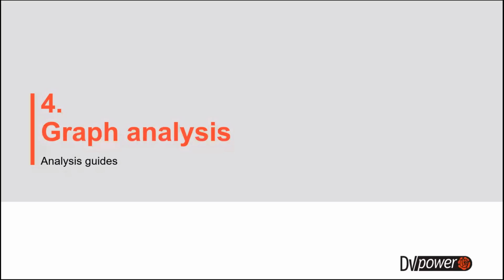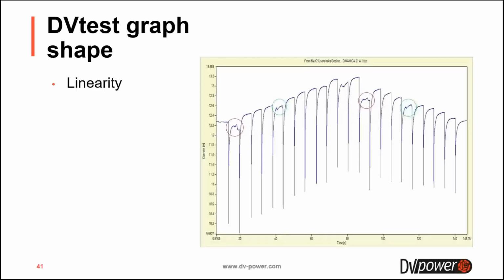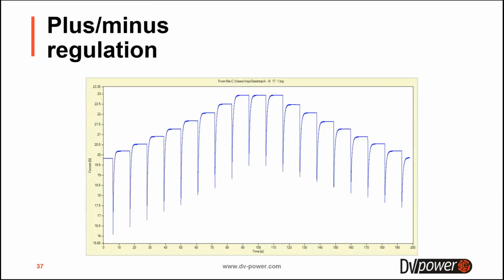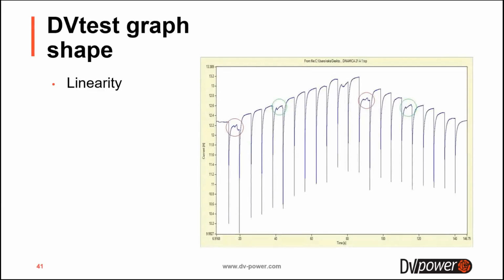Okay, we continue with some guides for analyzing the results. The first thing you need to look at is the linearity of the graph shape. Let's get back to this one. You can see here the upper part of the graph is linear, very smooth. It has a constant increase and constant decrease of the current. But if you look here, obviously you can see that the graph shape is not linear. You have certain transitions where the current is not stable, is not smooth, and that represents a problem. If you analyze further, you can see that the parts marked with the red circle are physically the same tap, and the transition taps marked with the green are actually the same tap.